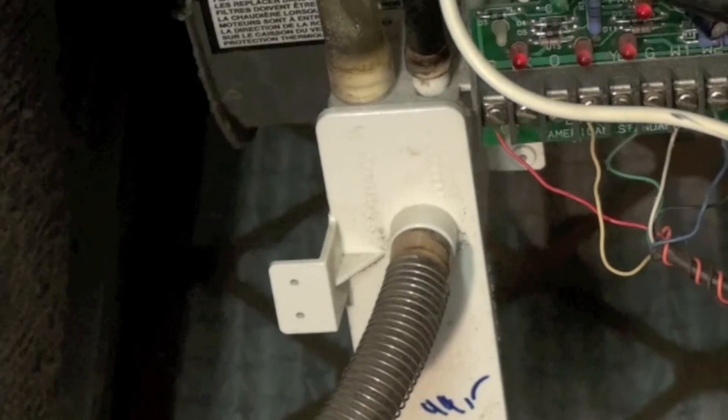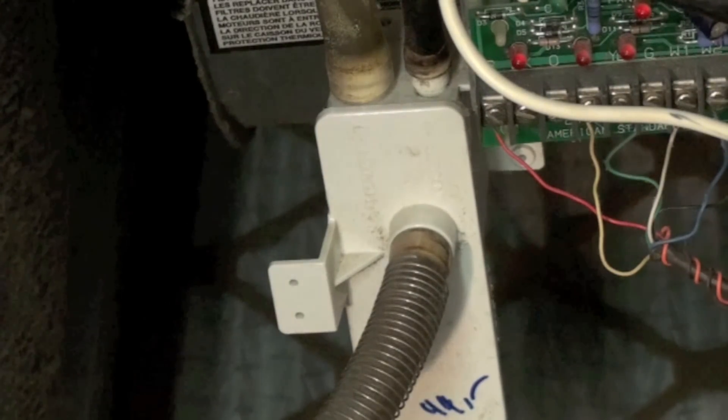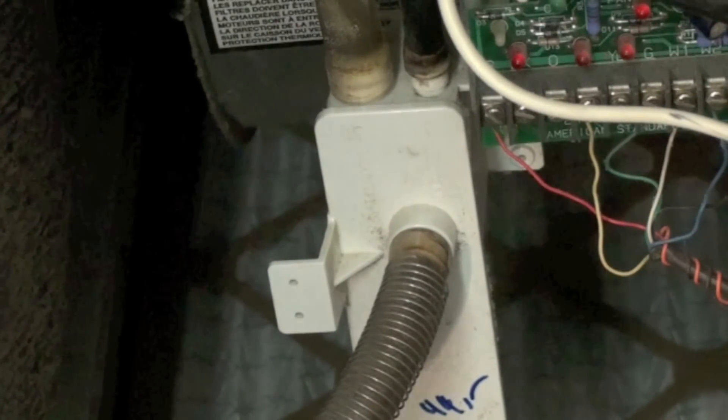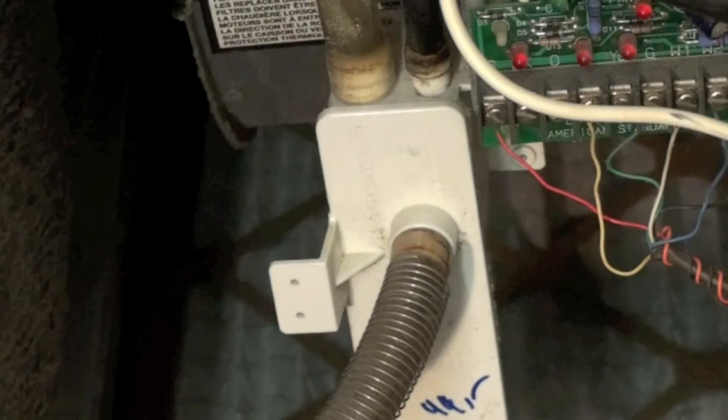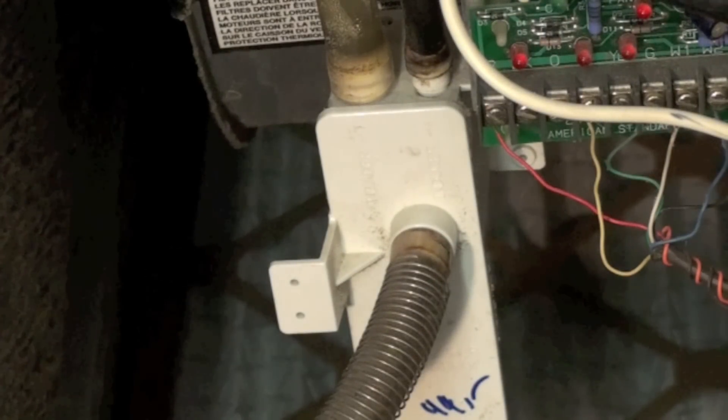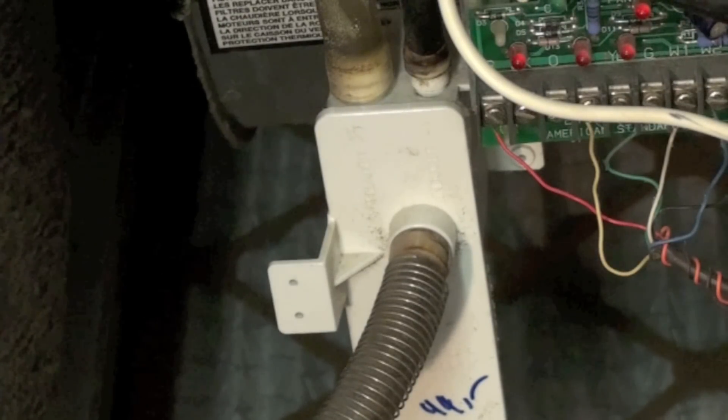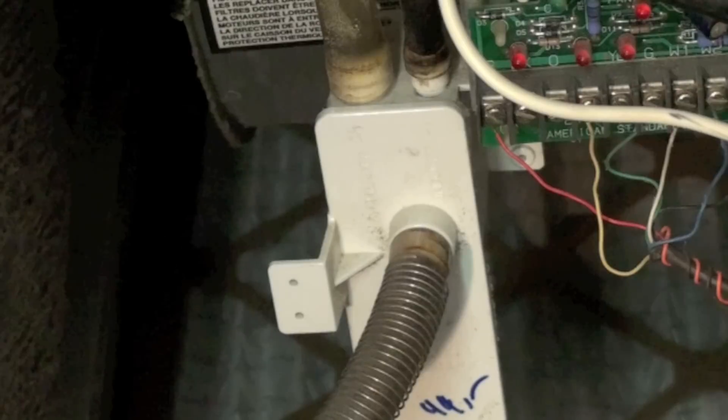So you would change the anticipator and usually it has something that says longer cycles and point it towards longer cycles. Move it about a quarter inch, see if that solves it. If it doesn't, move it another quarter inch. And that's about it for short cycling on gas furnaces. Simple things that you can check. Some of them will involve some expensive repairs.